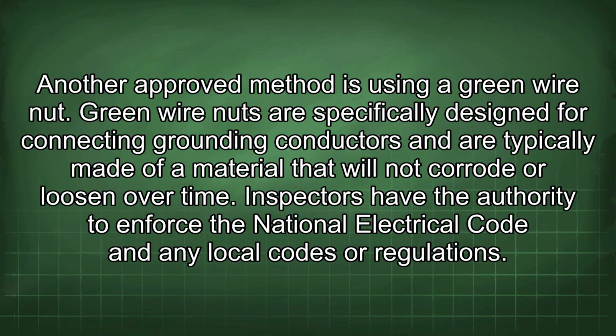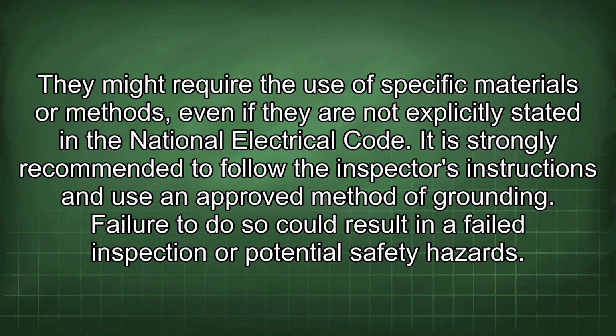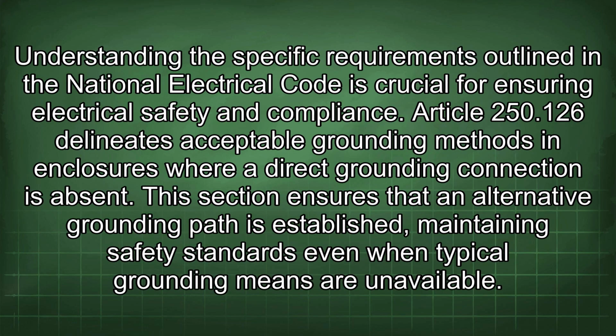Another approved method is using a green wire nut. Green wire nuts are specifically designed for connecting grounding conductors and are typically made of a material that will not corrode or loosen over time. Inspectors have the authority to enforce the National Electrical Code and any local codes or regulations. They might require the use of specific materials or methods, even if they are not explicitly stated in the National Electrical Code. It is strongly recommended to follow the inspector's instructions and use an approved method of grounding. Failure to do so could result in a failed inspection or potential safety hazards. Understanding the specific requirements outlined in the National Electrical Code is crucial for ensuring electrical safety and compliance.